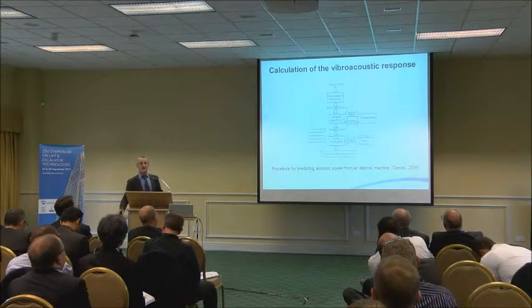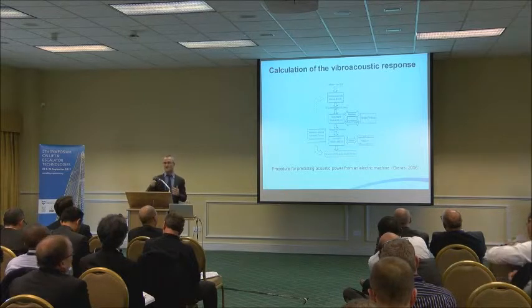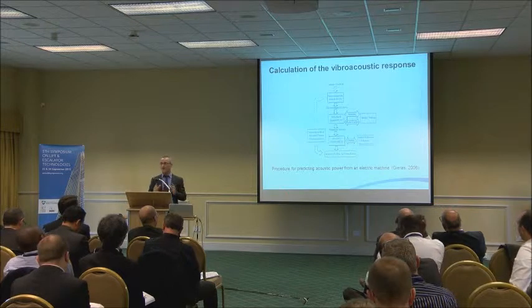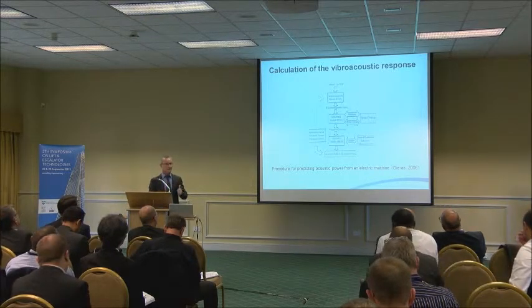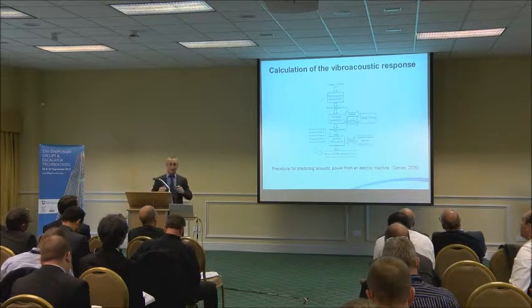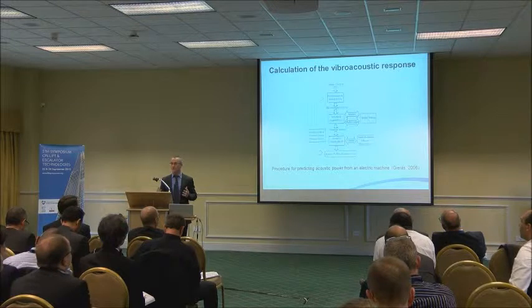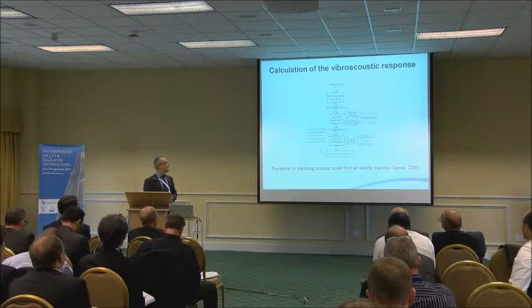If you go to the literature, the overall procedure consists of 3 steps. First, an electromagnetic model of the machine to calculate those electromagnetic forces at the air gap. The second one would be developing a structural model of the machine with all the components, stator, windings, ends, rotor, shaft, which must be updated according to experimental measurements.